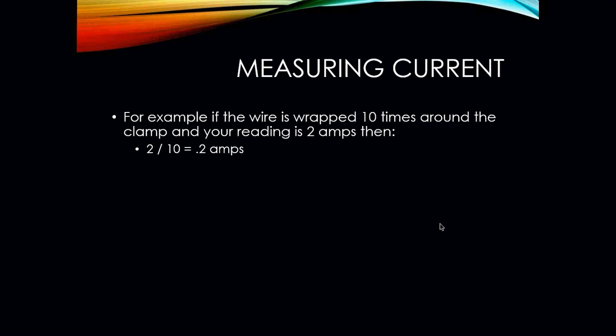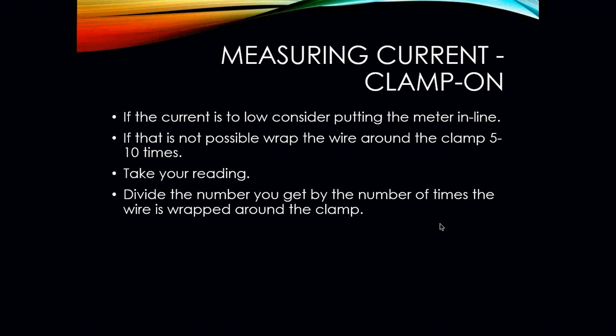Okay, for example here, if you have a wire and it's wrapped 10 times around the clamp and your reading is 2 amps, you take those two numbers, you divide it, and in this case it is 0.2 amps. If the current is too low, consider putting the meter in line. Okay, and if that is not possible, you may want to wrap the wire around 5 to 10 times around the clamp-on part of the meter if you have to. Do the following math problem and take a reading. Divide the number you get by the number of times the wire is actually wrapped, and you will get an amp reading.